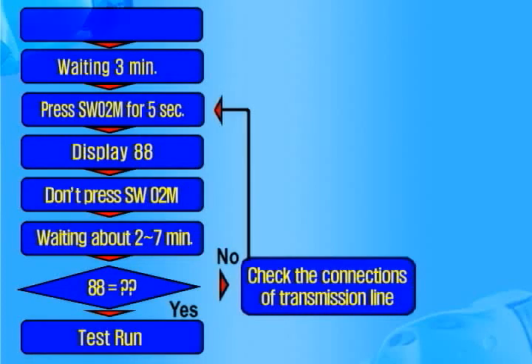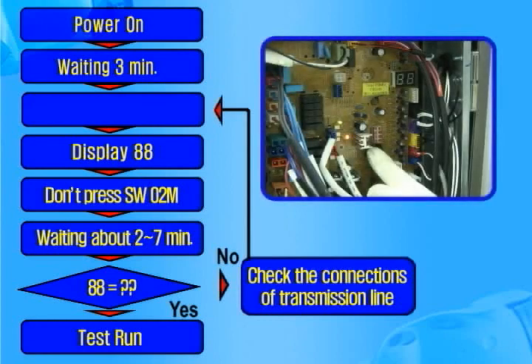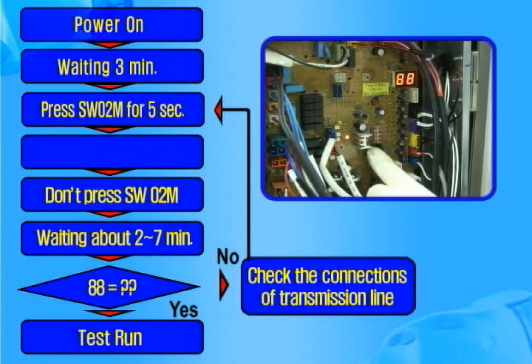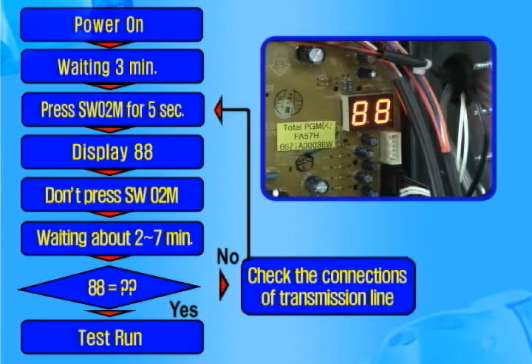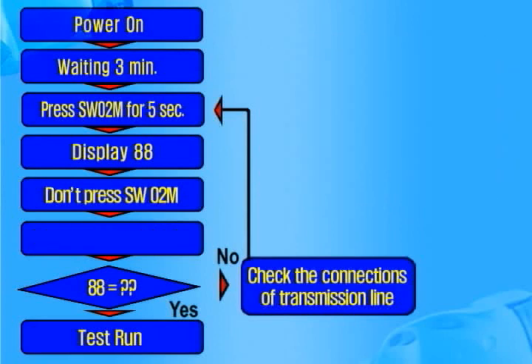To make auto addressing process, wait 3 minutes after the power on. And press SW02M switch on the control board for 5 seconds. Then the indoor unit auto addressing will start indicating 88 on the segment LED. This addressing takes from 2 to 7 minutes depending on the numbers of indoor units.